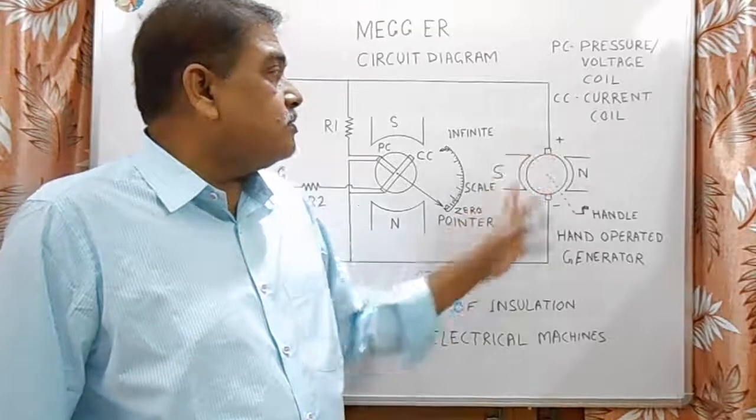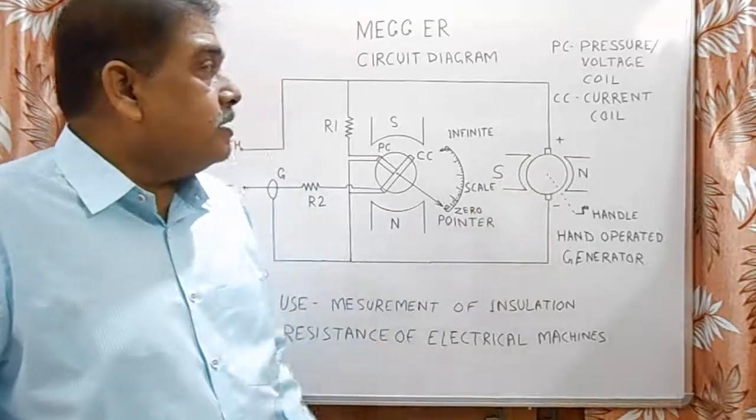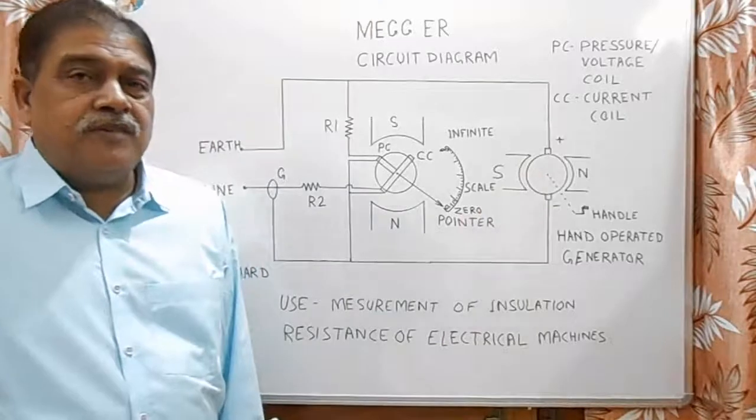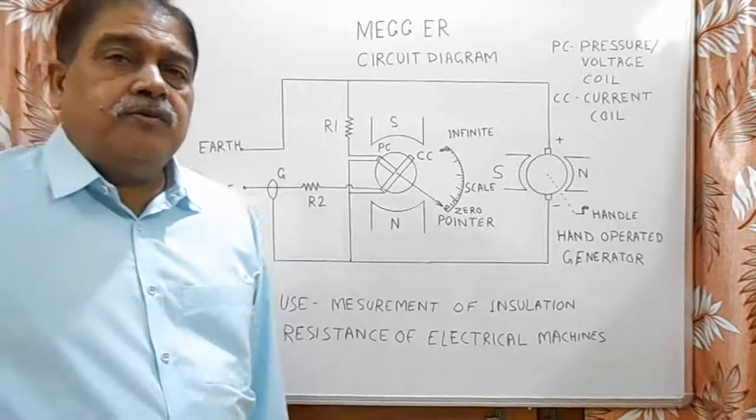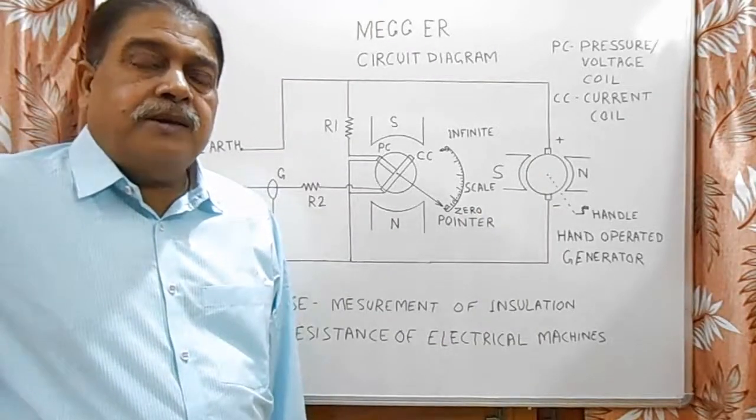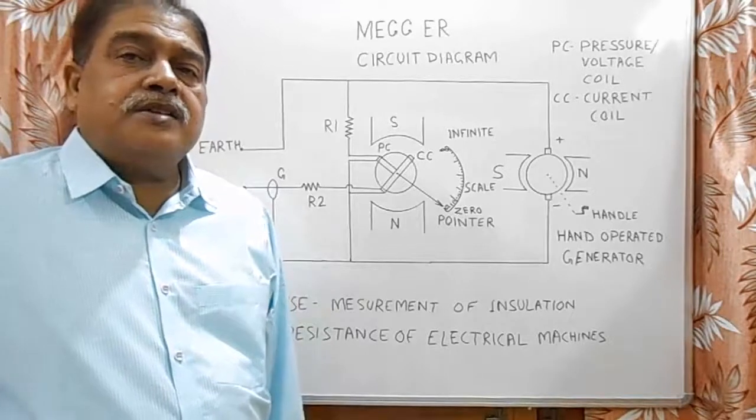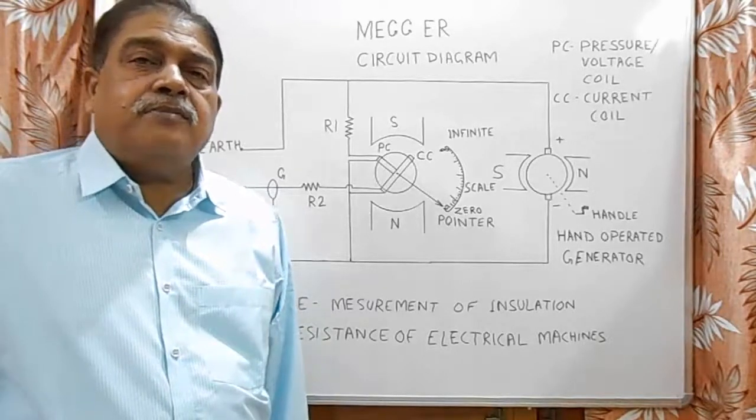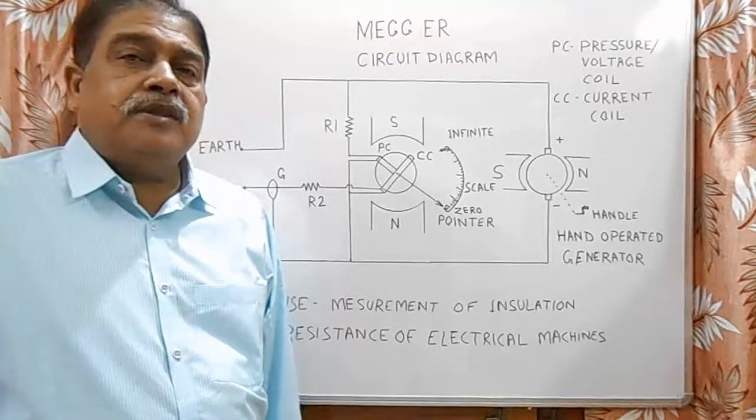So it gives a constant voltage for working of Megger. Here Megger comes in different ranges: 50V, 250V, 500V, 1000V, and for HD machines it comes in 2.5kV and 5kV range.